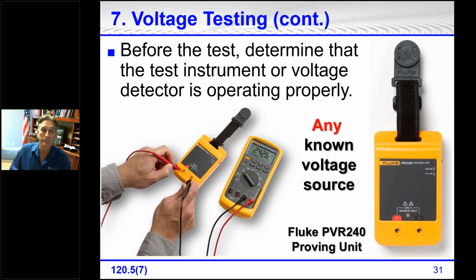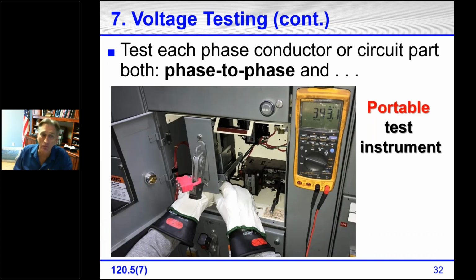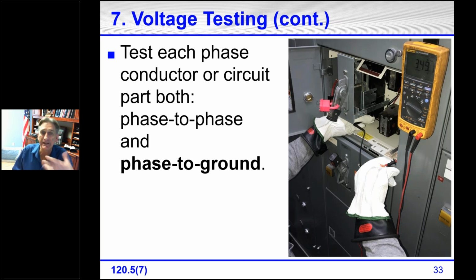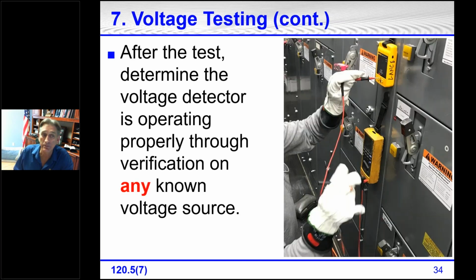But before the test, you make sure the meter's working. Then you're testing for the absence of voltage. How do we do it? Phase to phase and phase to ground. And then what? After the test, we also make sure the meter is working properly on any known voltage source. It doesn't have to be the same voltage you're working with.